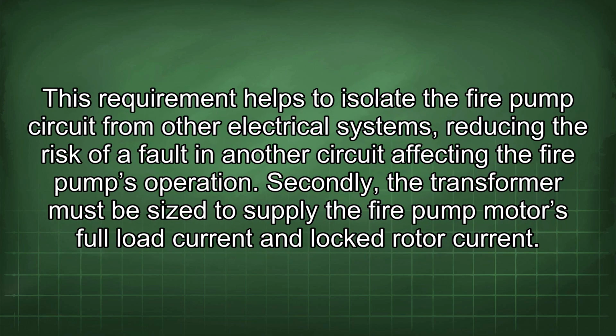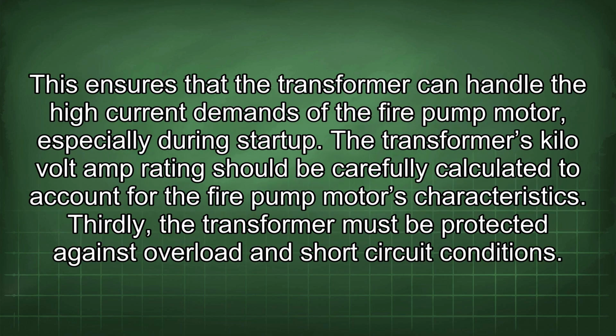This requirement helps to isolate the fire pump circuit from other electrical systems, reducing the risk of a fault in another circuit affecting the fire pump's operation. Secondly, the transformer must be sized to supply the fire pump motor's full load current and locked rotor current. This ensures that the transformer can handle the high current demands of the fire pump motor, especially during startup. The transformer's kilovolt amp rating should be carefully calculated to account for the fire pump motor's characteristics.